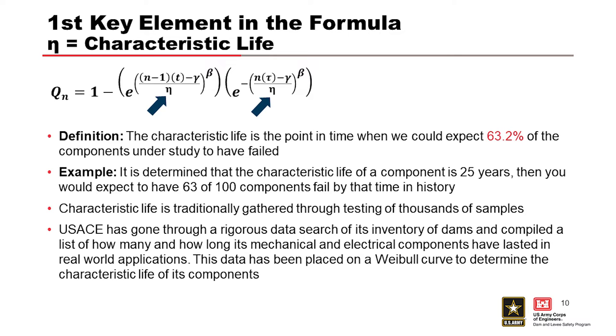To talk about some of these parameters, the eta is the characteristic life. The definition is the characteristic life is the point in time on the Weibull curve that we'd expect 63.2% of the components under study to have failed.